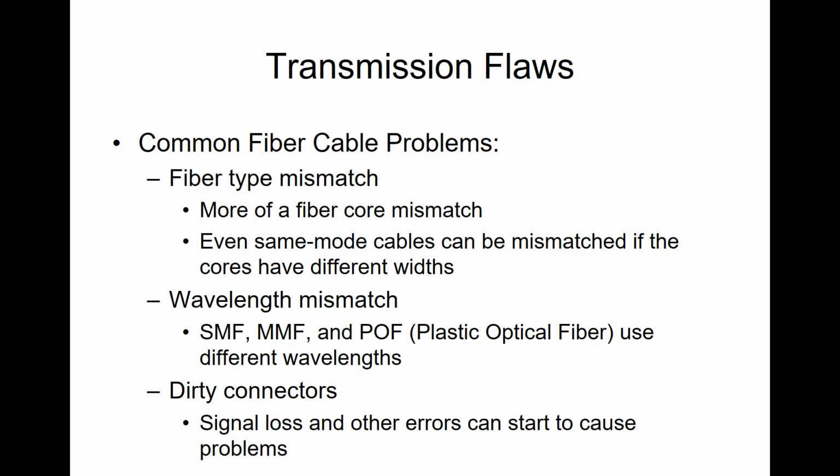But again, I told you about that job down in Falls City, and quite frankly, the contractor screwed up putting in the fiber in there. And the transceivers and the things that we had specified, because on top of that drawing, we had a whole request of items and a list of what was needed. And we already had equipment bought, and the fiber that they brought in and our transceivers were not a match.